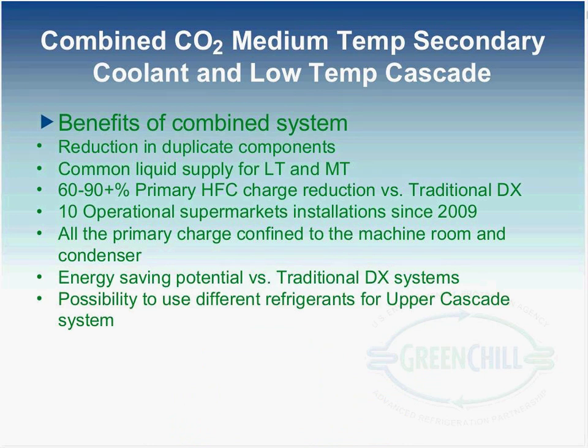The benefits of this combined system is obviously the reduction in duplicate components of the cascade and the heat exchangers and the pressure vessels. We also have a common liquid supply for low and medium temp. That will reduce the overall copper that's required to pipe or install the system. Then there's going to be the 60-90% reduction in the primary HFC charge versus a traditional DX system. And this is pretty easy to attain because there's no low temperature HFC refrigerant required anymore except in the condenser. So all the low temp is CO2. All the refrigerant in the sales floor, in the back room, coolers and freezers is CO2. And the HFC charge is in the machine room and the condenser.